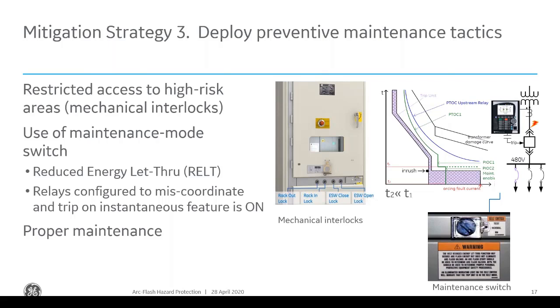The energy reducing maintenance switch is a very simple but effective solution that's described in a lot of the standards as one of the techniques approved for arc flash mitigation. What it basically does is decrease the fault clearing time, and thus the incident energy is reduced greatly during what we refer to as maintenance mode. In the picture on the right, the relay trips without intentional delay when the maintenance switch is enabled and a fault occurs. So you have some sort of switch, push button, or SCADA control to bypass any coordination that this main breaker needs to do with the downstream breakers, and it will go into strict instantaneous overcurrent mode. So whenever there's a short circuit or arc flash, it will trip the main breaker right away.